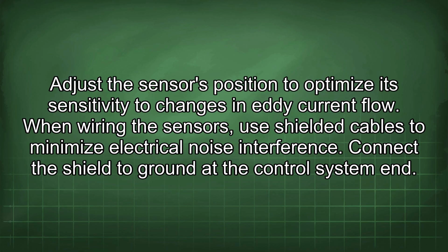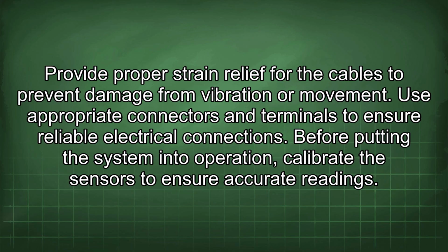When wiring the sensors, use shielded cables to minimize electrical noise interference. Connect the shield to ground at the control system end. Provide proper strain relief for the cables to prevent damage from vibration or movement. Use appropriate connectors and terminals to ensure reliable electrical connections.